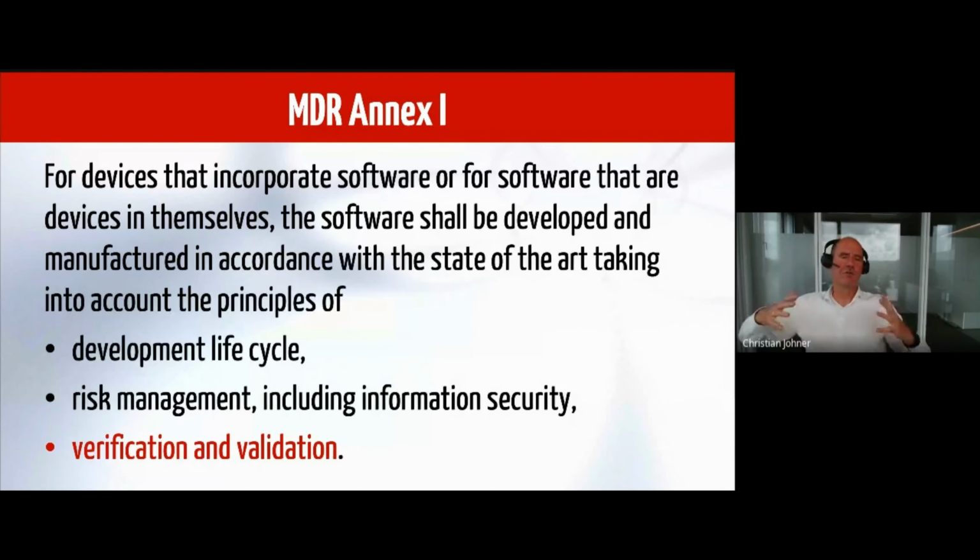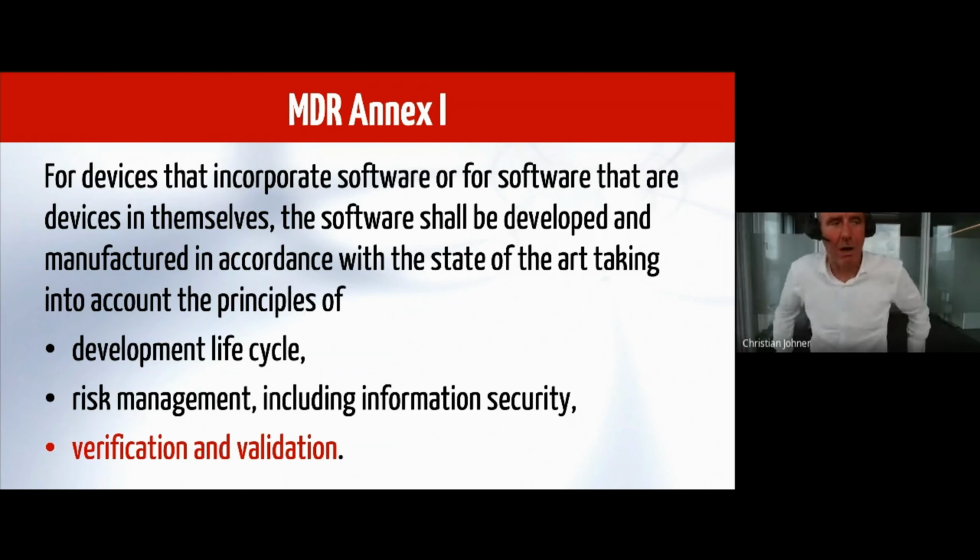And the most well-known sentence inside the MDR, that's Annex I, I think 17.3 or 17.2, says whenever you have a device which contains software, we have to develop it state of the art and also care about development life cycles, risk management, IT security, and verification and validation. I would like to dive a little bit into this verification and validation part.